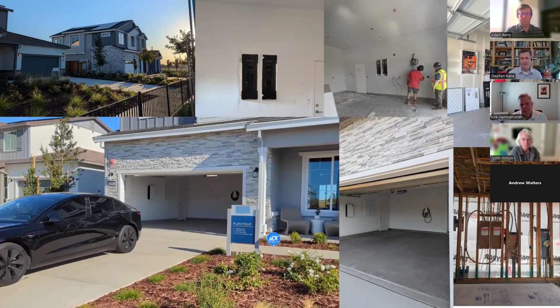We've found in some markets it can be $3,000 to $12,000 per lot to bring in 320 or 400 amp service. In other places, Tennessee, the Midwest, places out east, there's no net difference to a builder or a customer to go from 200 to 320 or 400 amp service. So it's really site dependent, and it's not just one particular utility.